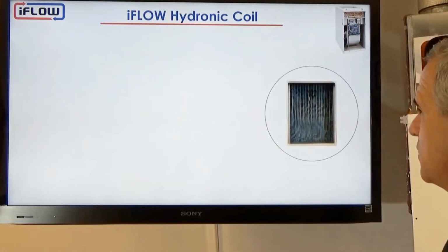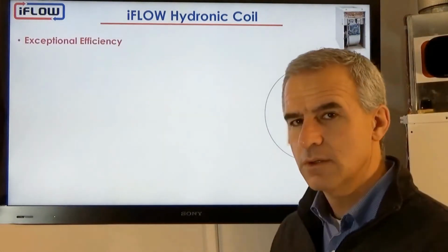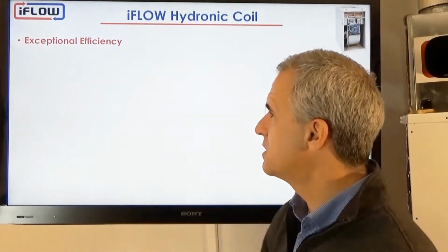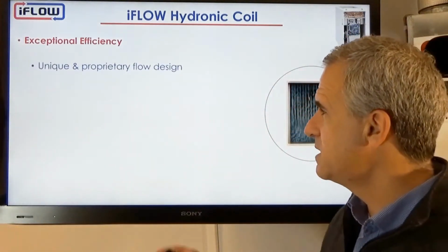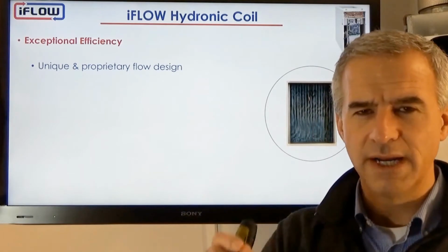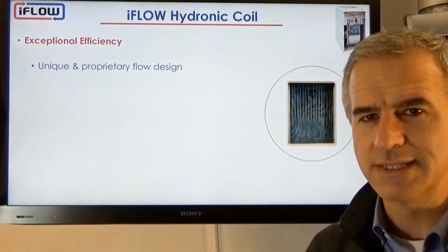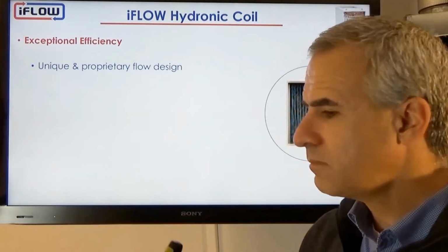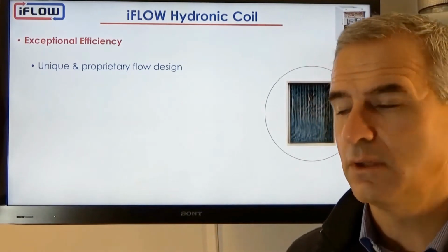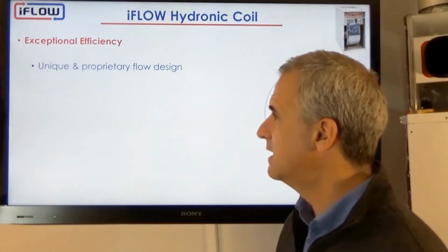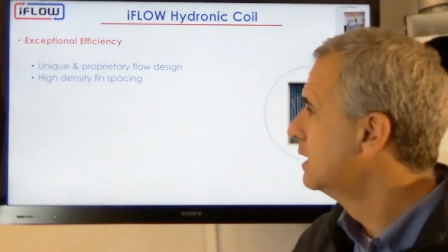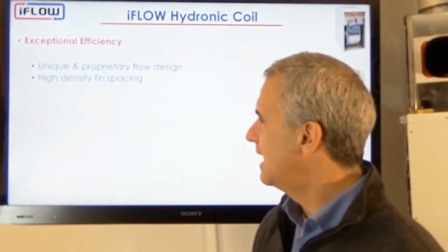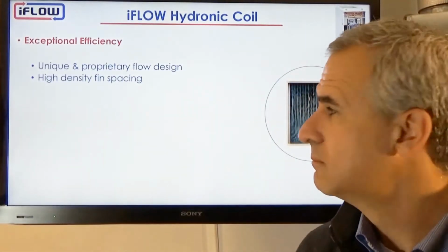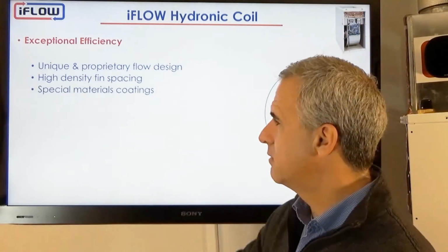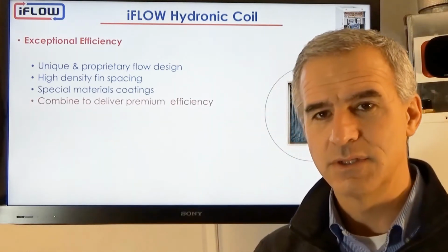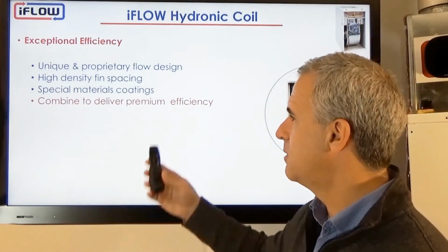So let's break each of those down a little further. So I mentioned we get exceptional efficiency off our coil. Basically we have a unique and proprietary water flow pattern. So that design is unique in the industry, unique to iFLOW, all designed in-house in Toronto. We have a high density fin spacing, and that combined with special materials coating allows us to deliver premium efficiency.